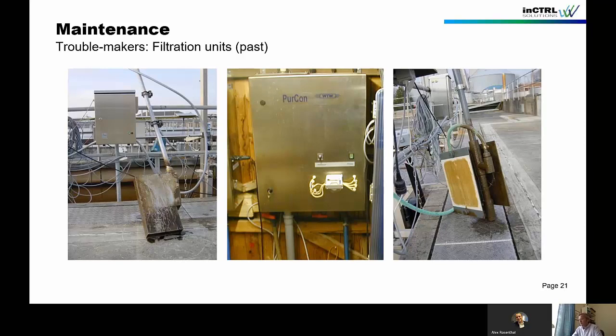And you have these big submerged pumps, and then depending on the pump rate, and we had quite a high pump rate, but still, due to the high volume, that unit added quite a bit to the response time of the analyzer, right? So in the first pump we used, we ended up with a response time of over 40 minutes for an ammonia analyzer. So be careful with that. Otherwise, quite a robust instrument.